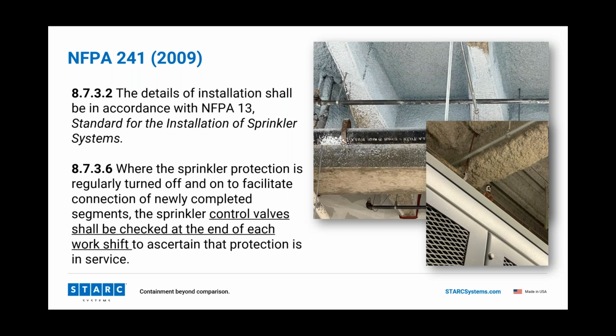Okay, so let's look at a few examples here for the sprinkler system side. One thing that's also often missed is that you can't just remove the ceiling and just leave the sprinklers in place. You have to bring that sprinkler system, if it's an existing system, up to NFPA 13 in order for it to be an approved, as we just saw on the previous slide, an approved sprinkler system.